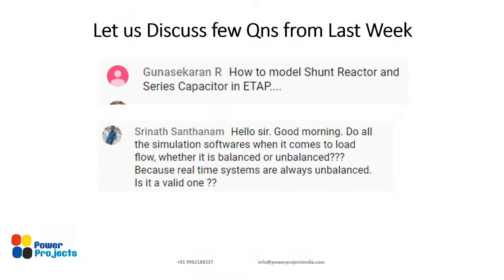How to model a shunt reactor and a series capacitor? For the shunt reactor, I think we explained last week. There is no direct shunt reactor available in ETAP, so you have to model it as a lumped load with zero power factor, so that it consumes reactive power. You should model it as a constant impedance load, because the reactor is a constant impedance. Or you can take a static load and model it with a zero power factor. So that's how you have to model it.